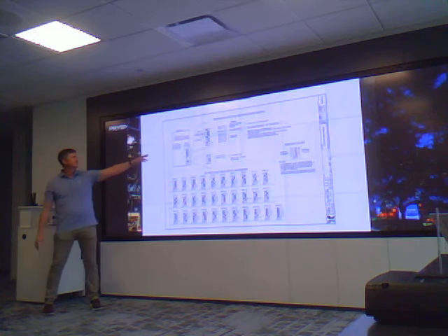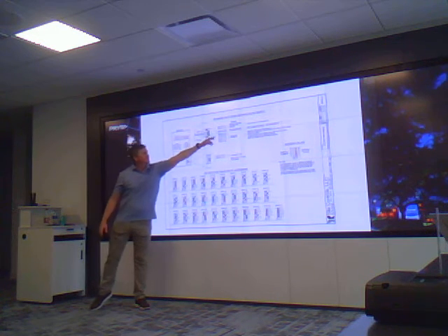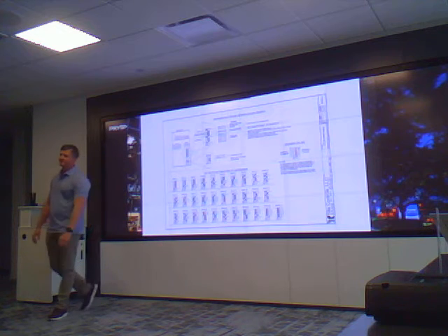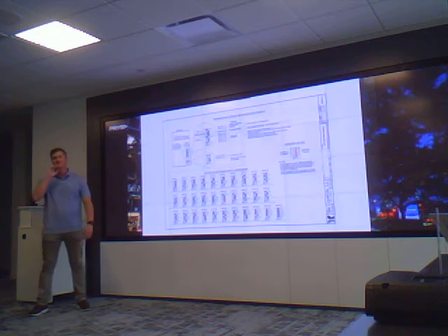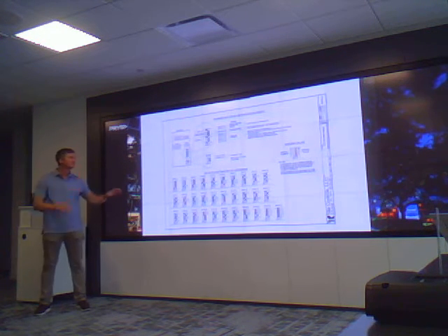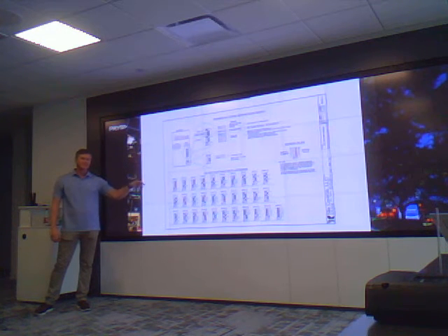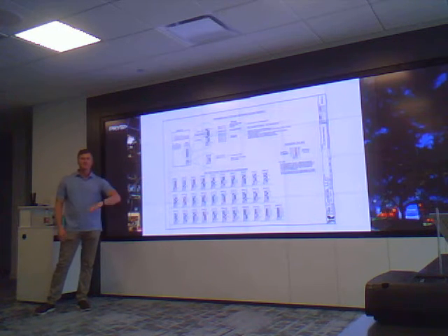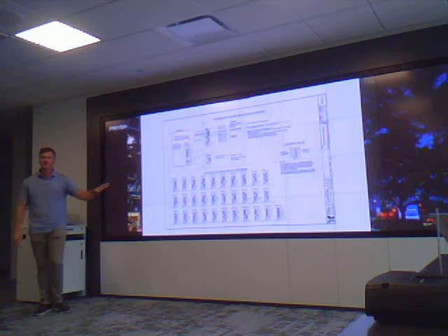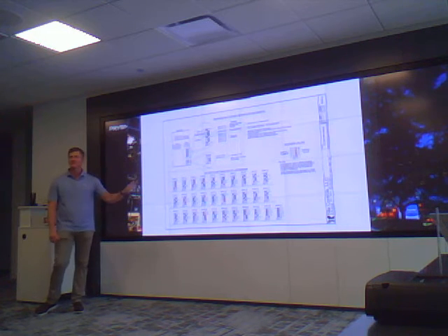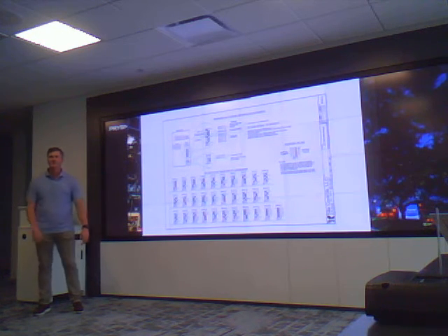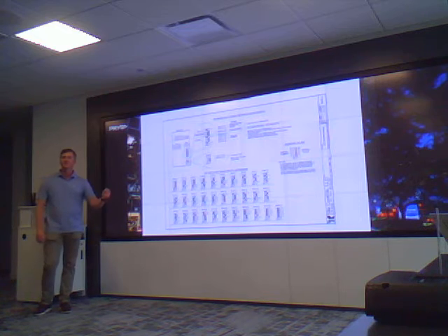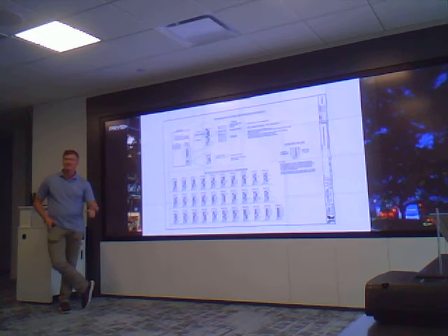And you can see where it says on 6, it's for if you have a separate temperature sensor. That's on the DZC in space. The new RTU DZC RTs are already preset to have a zone temp sensor wired to them. So dip switch 6 does not need to be selected or turned on for that. 6 is part of the addressing of the unit, not for switching back and forth to a remote.